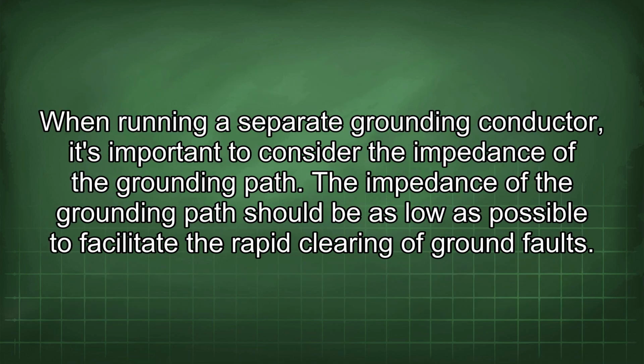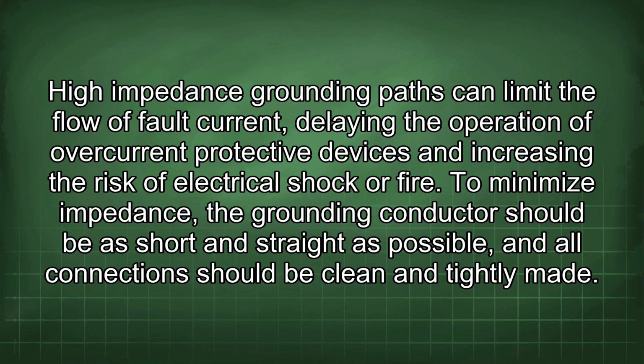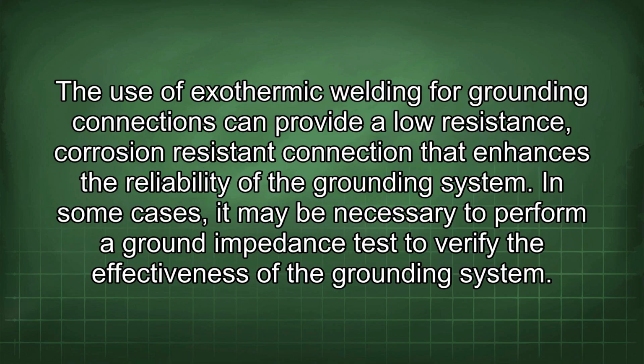When running a separate grounding conductor, it's important to consider the impedance of the grounding path. The impedance of the grounding path should be as low as possible to facilitate the rapid clearing of ground faults. High impedance grounding paths can limit the flow of fault current, delaying the operation of overcurrent protective devices and increasing the risk of electrical shock or fire. To minimize impedance, the grounding conductor should be as short and straight as possible, and all connections should be clean and tightly made. The use of exothermic welding for grounding connections can provide a low-resistance, corrosion-resistant connection that enhances the reliability of the grounding system.